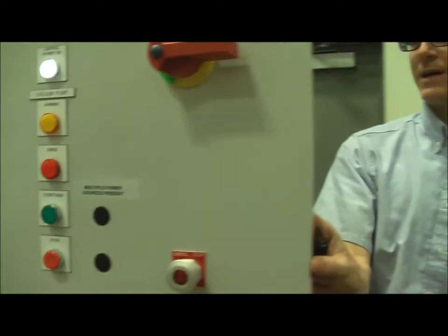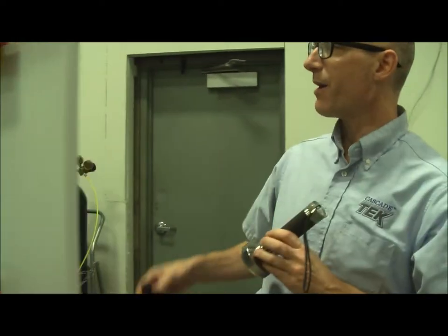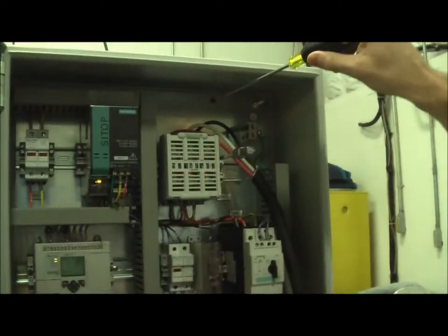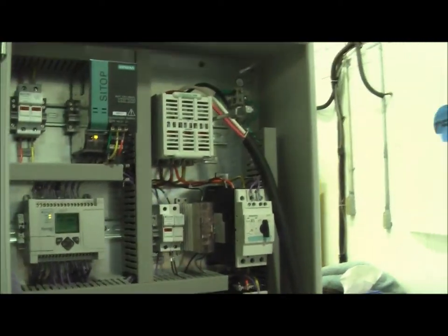If for some reason it's going backwards, then we can come inside the panel, turn the power off, and then we'll just switch any two of the incoming phases to reverse the pump's rotation.